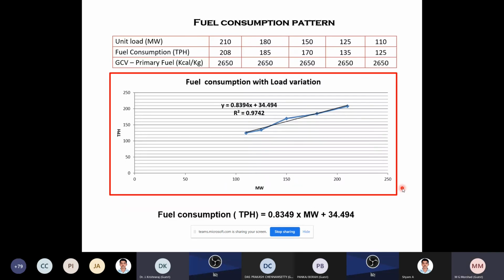Now, fuel consumption pattern. It is very, very important because we do not know what the pattern of fuel consumption is. Normally, during the PG test, it will be established. After that, nobody will establish this one. So this is one opportunity. During energy audit, it can be established. But one thing is, the unit has to be run at various loads. If it is permitted, if it is possible, you can check it.